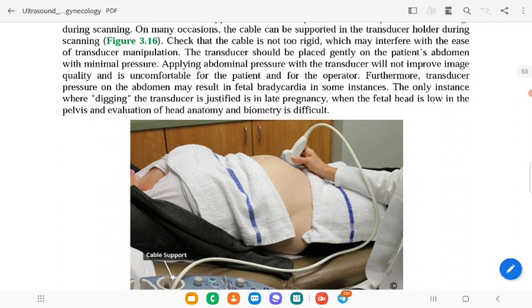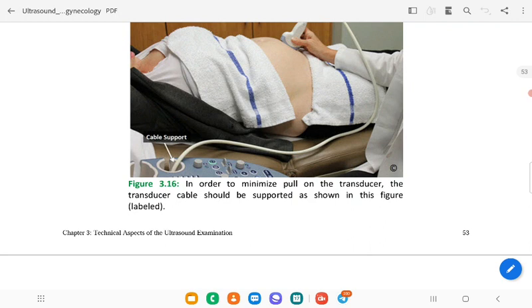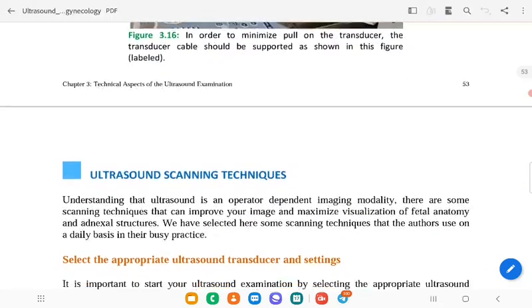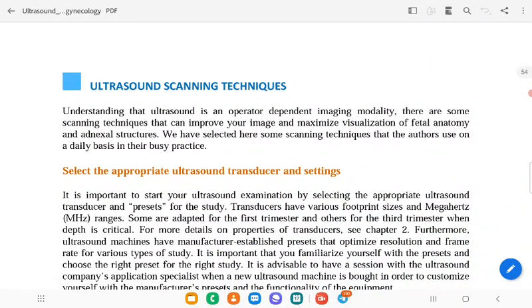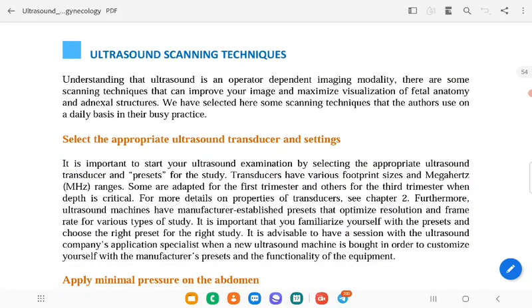The only instance where digging in with the transducer is justified is in late pregnancy, when the fetal head is low in the pelvis and evaluation of the anatomy and biometry is difficult. In order to minimize the pull, the transducer cables should be supported as shown in this picture. The ultrasound scanning technique. Understand that ultrasound is an operator-dependent imaging modality. There are some scanning techniques that can improve your image and maximize visualization of fetal anatomy and adnexal structures. We have selected here some scanning techniques that the authors use on a daily basis in their busy practice.